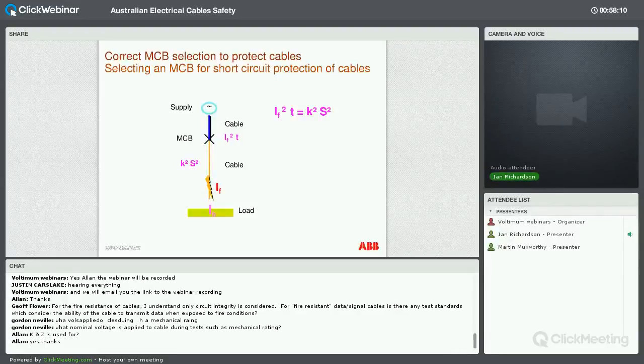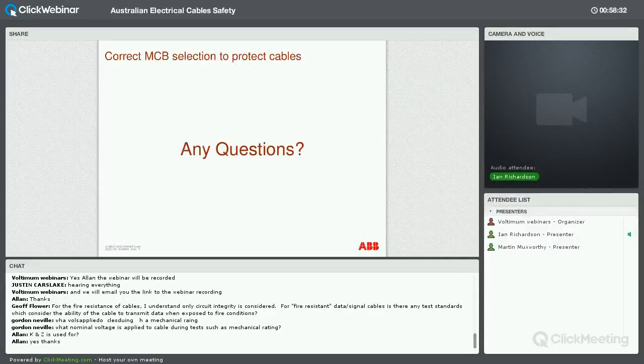But the main message out of this is the most important thing is to make sure that you're selecting the appropriate protective device against the cable, or if you've already got a protective device, you choose the correct cable for that protective device. Depends which way you're approaching it. So that, in fact, is a fairly brief overview from my side on selecting the correct breaker. If there's any questions, by all means, please ask.